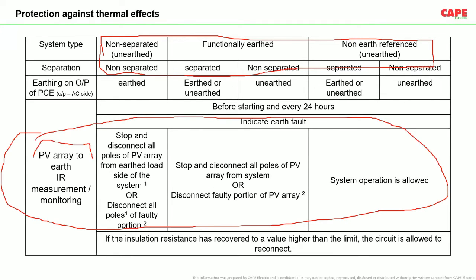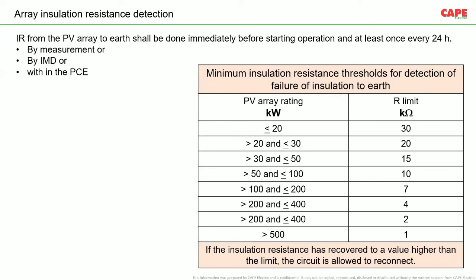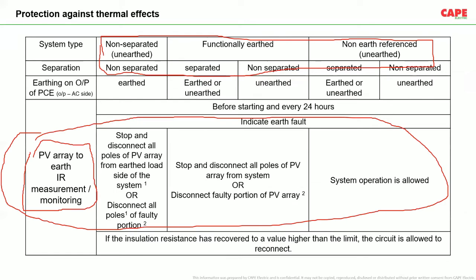Say, for example, PV array to earth insulation resistance monitoring. One of the safety measures included is insulation resistance monitoring. That means the PV array, depending upon its capacity, should have a certain minimum insulation resistance. For example, up to 20 kilowatt, 30 kilo ohm insulation resistance, and for more than 500 kilowatt, 1 kilo ohm insulation resistance is required. So the insulation resistance of the system is measured, and if the insulation indicates an earth fault, see here the safety measure: stop and disconnect all poles of the PV array from the earthed load side of the system.